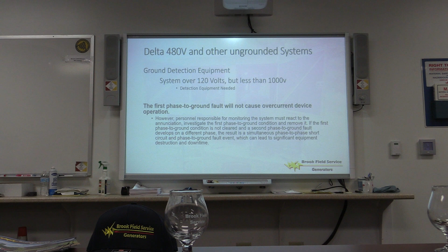The circuit breakers must typically have a straight voltage rating of 480, as opposed to 480/277, which is probably what is being installed in these places because that's the most common breaker that people are accustomed to. It's very rare that we run into a straight 480 volt breaker. If you have this type of system, you have to have ground detection equipment. This is something that we have not come across, finding any ground detection on these systems. So it's almost non-existent here in Vermont. Next one.